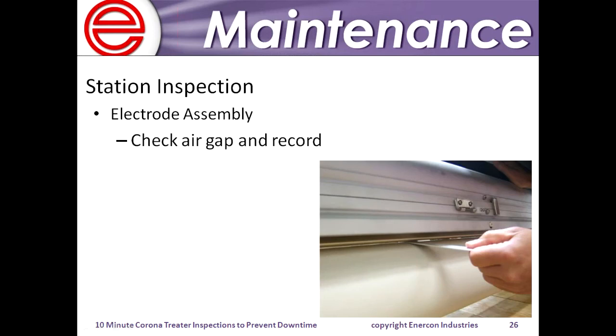And again, once we're all set, we want to check and record the electrode air gap. We do recommend 1.5 millimeter or 60 thousandths between the ground roll and the electrode. Or you might want to go back to your baseline, whatever you use there. But our recommendation is 60 thousandths of an inch. And if it does require electrode gap adjustment, that's another procedure outlined in the manual, or other forms of media that we offer, or you can always call and ask us.